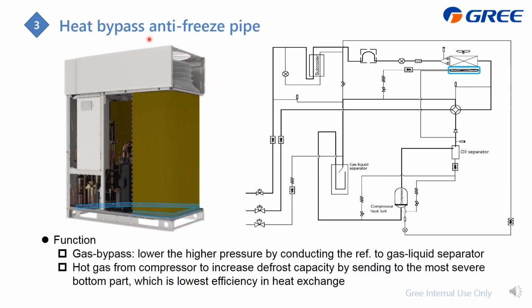Heat bypass antifreeze pipe. That means at the bottom of the outdoor heat exchanger, it is another cycle, which is not the same as the upper side. Also, you can find that at the outdoor heat exchanger for the top discharge, at the bottom side, the heat transfer efficiency is not that high because the air volume is not that high, as it is far away from the top fan. If it is far away, the air volume is not that high, which also indicates the heat transfer efficiency is not that high.